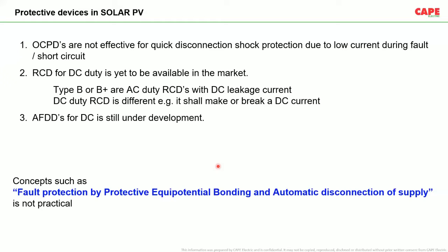Whereas this method will not work in solar PV, because for enabling automatic disconnection, you need a protective device which is able to operate within a certain time. A device that operates within that time, let's say, for example, 0.1 second or 0.2 second, may not be possible. OCPDs are not effective for quick disconnection because of the lower current during disconnection. So shock protection by disconnection by OCPD is not possible.